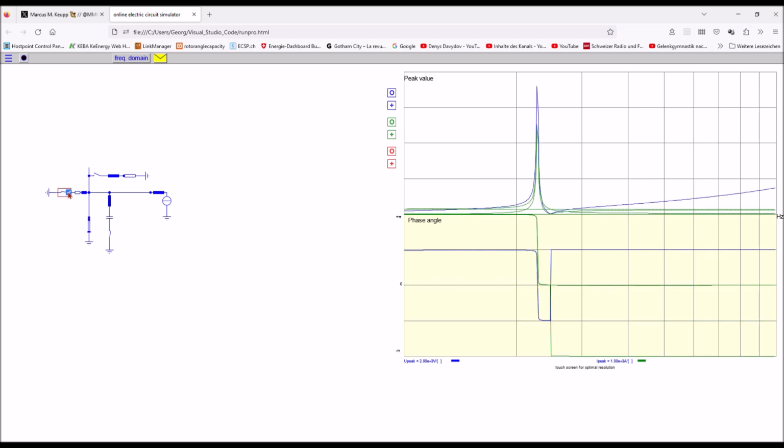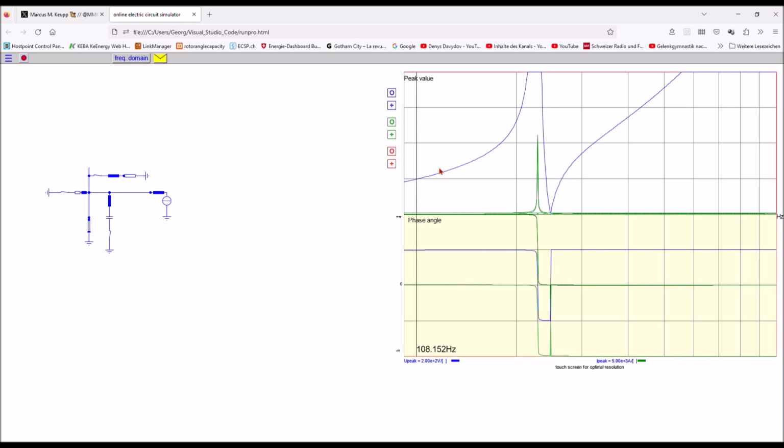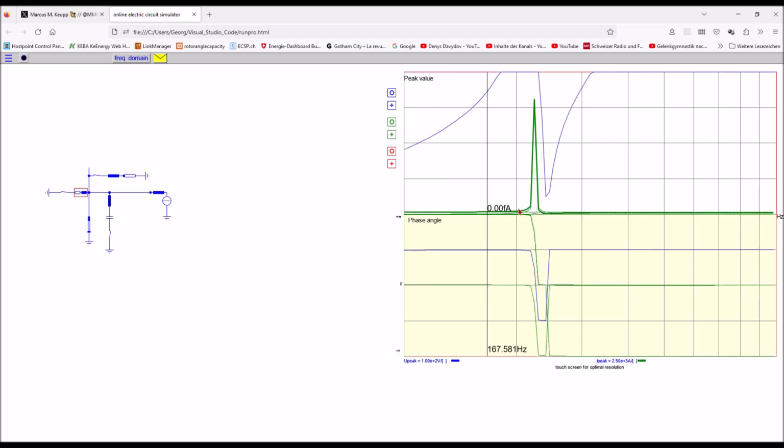When I reconnect the power supply side, I almost always get a resonance close to the filter frequency. This is dangerous. Therefore, I reduce the resonance frequency slightly below the harmonic frequency. So the filter is not optimal anymore, but I get more safety margin to the resonance.